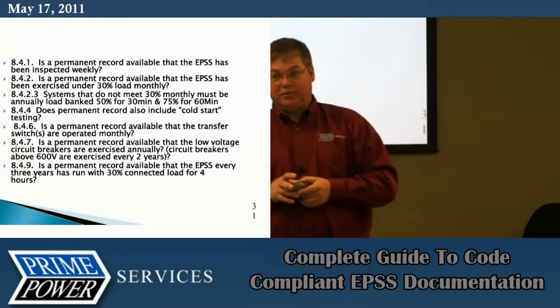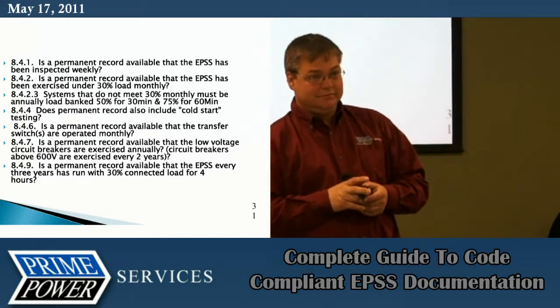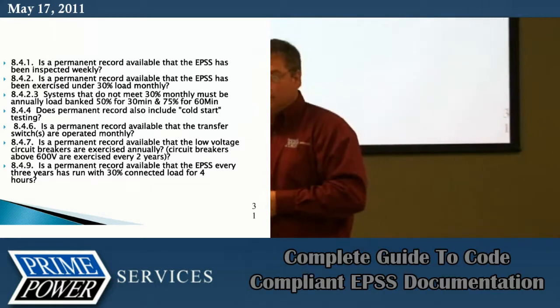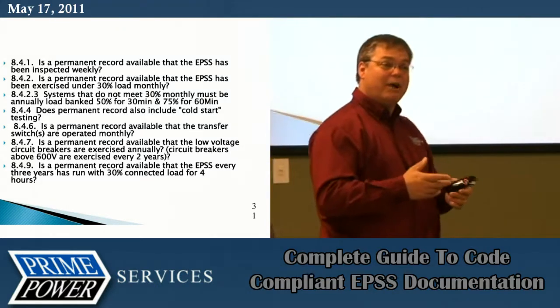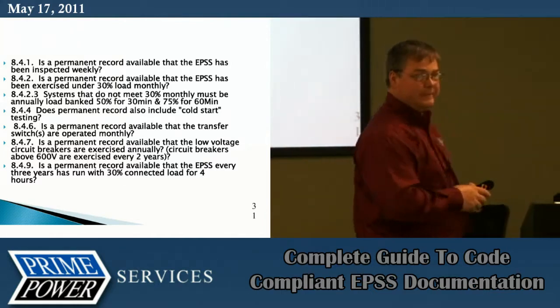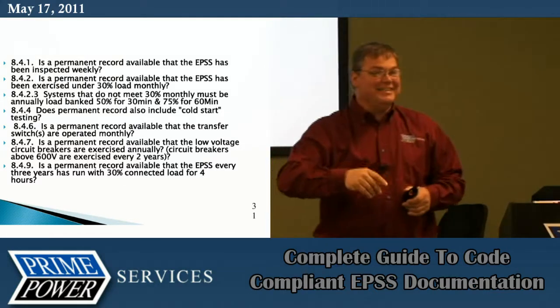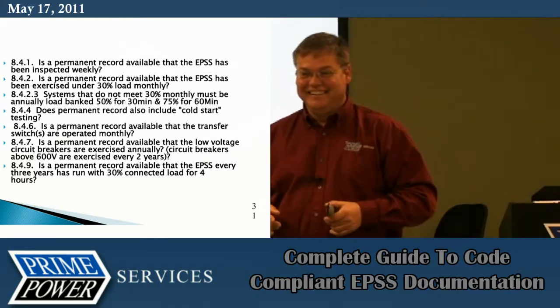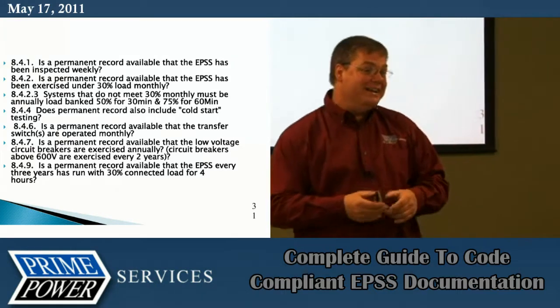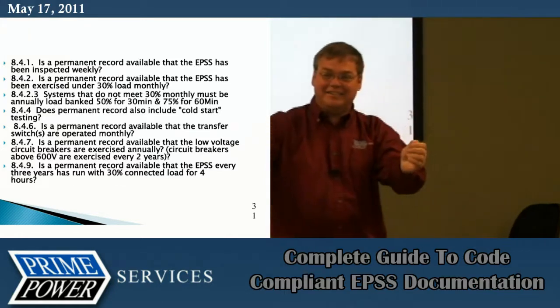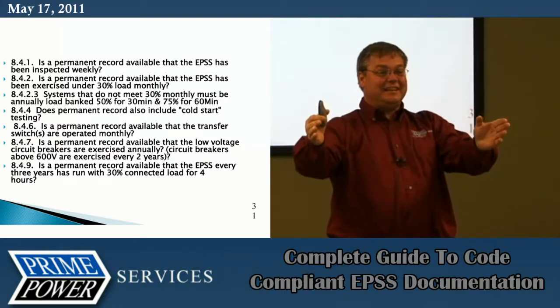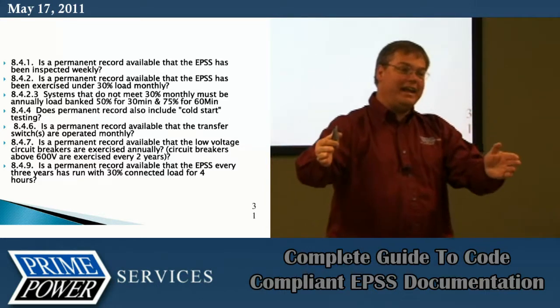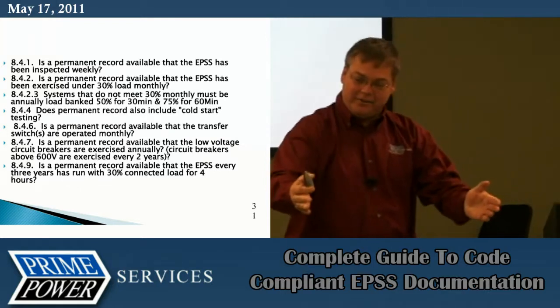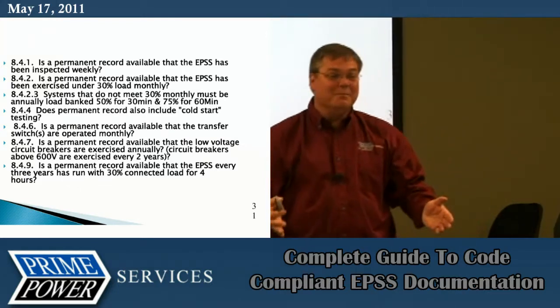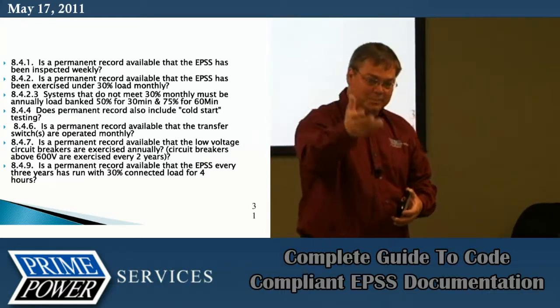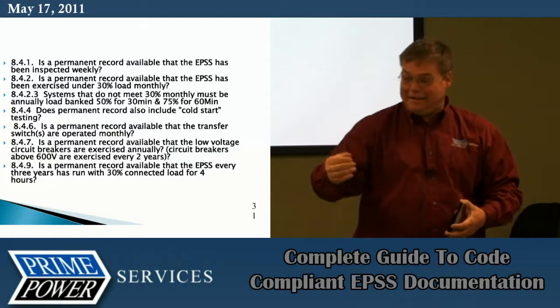So I ask, what does the 0.2 mean? 2/10 of an hour. You'd be surprised at people that say, well, I don't know. It's 2/10 of an hour. What's a tenth of an hour? 6 minutes. Had you thinking on that one, didn't I? I answered the first one. 6 minutes. So if it started at 0.2 and went to 0.8, that's 6 ticks. 6 times 6 is... Now, see, I had to figure all that out as an inspector. I'd rather just say it started at 10 and cut off at 10:35. It's much easier. But there are people out there in your positions that are actually doing that testing that can't tell you a tenth of an hour.